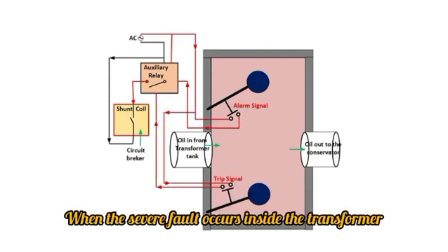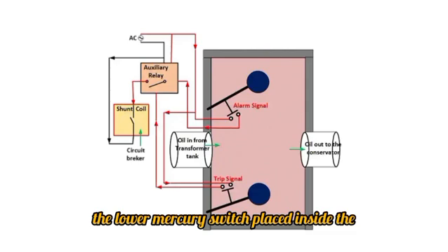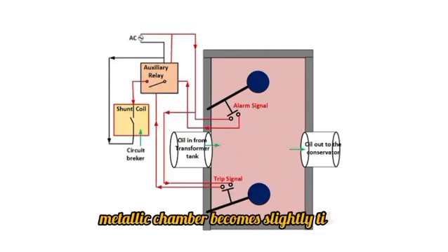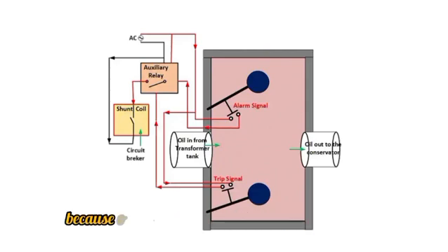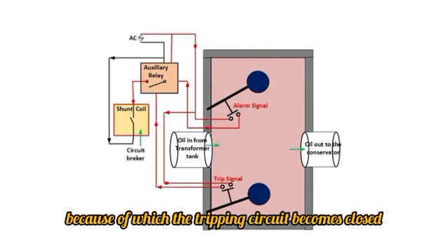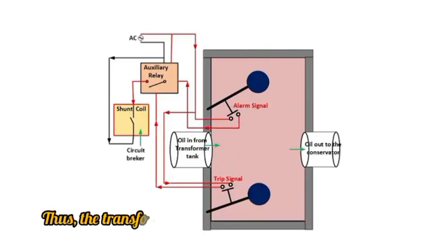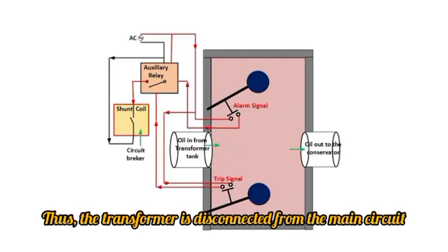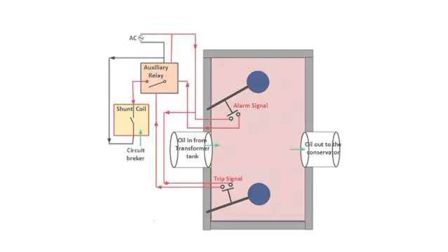When a severe fault occurs inside the transformer, the lower mercury switch placed inside the metallic chamber becomes slightly tilted, because of which the tripping circuit becomes closed. Thus, the transformer is disconnected from the main circuit.